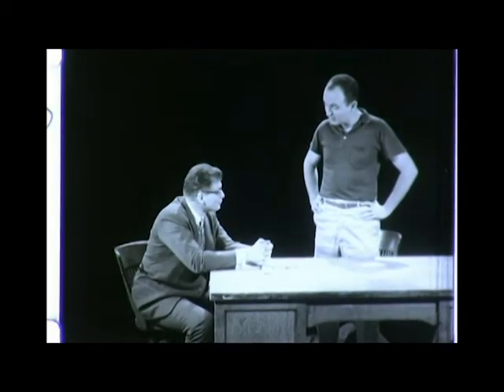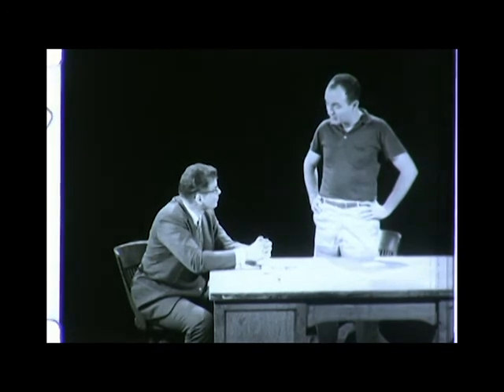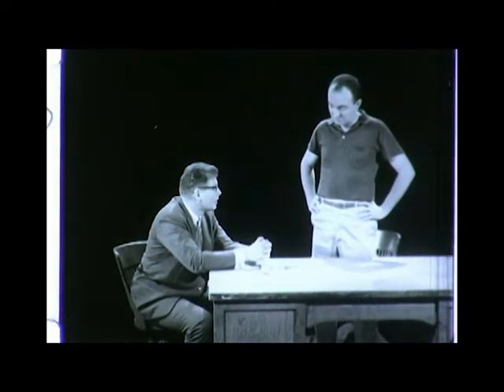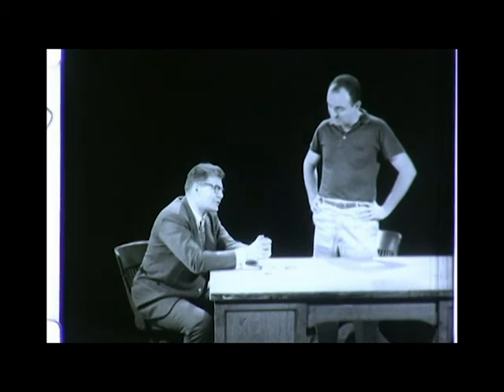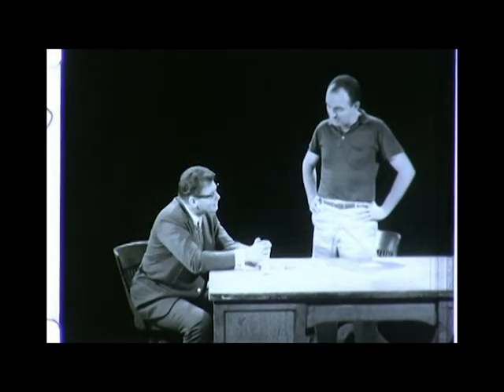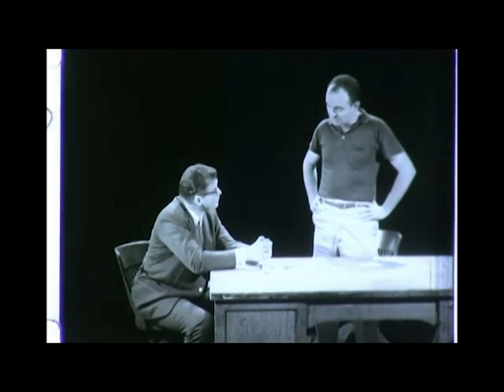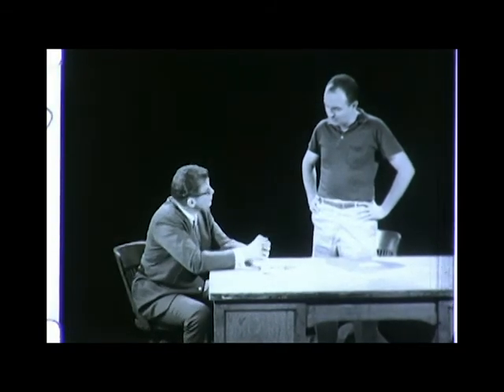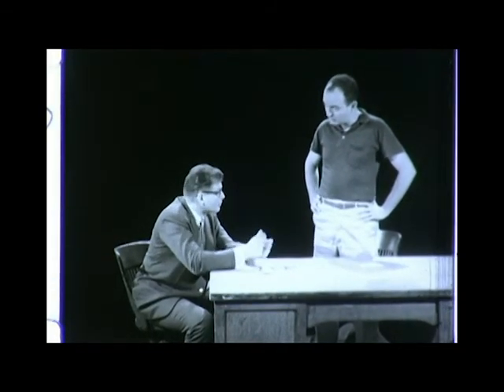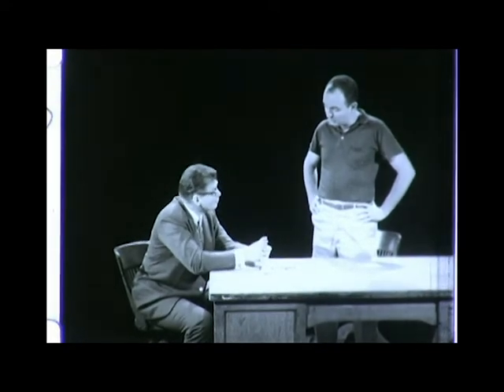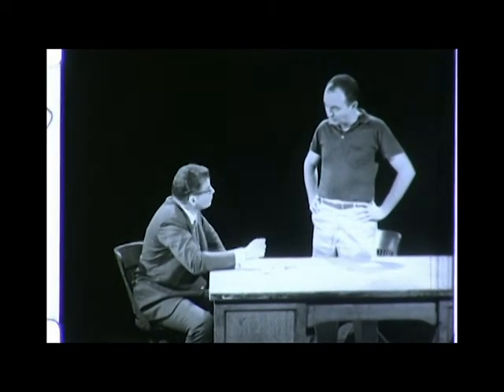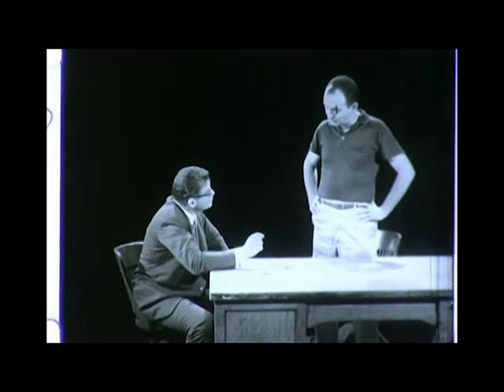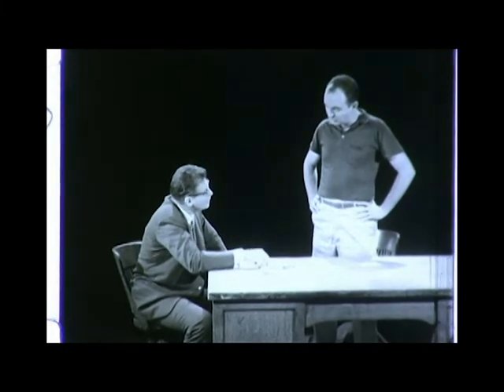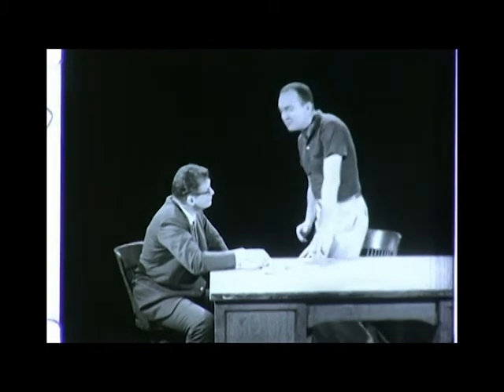Are you saying, then, that you wouldn't put any encapsulated motors in around here? Well, Eddie, the number of applications that really call for encapsulated motors is surprisingly small. Offhand, I can think of only one place in your plant where you might get your money's worth installing encapsulated motors. Where's that? Well, you know the shed where you wash down your gravel? Yeah. There isn't much dust there, but there is plenty of moisture. If you've had trouble with wet windings in your motors, encapsulation might be a good idea there. Yeah, they get wet all right.